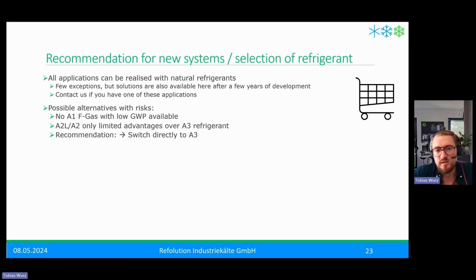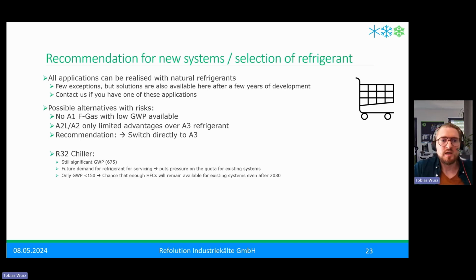Our recommendation is to switch directly to A3 because there's no way around it with other refrigerants in the future. For example, normal chillers, the propane chiller, propane heat pump will be the standard in 5 years at the latest. So if you switch to it today, you know, okay, it's possible. You have to take a look at the risk assessment, but if you have done it, it's no problem.